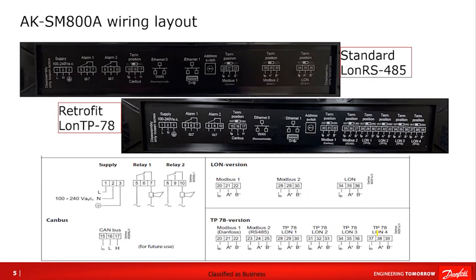On the back of the cover plates, you'll see a sticker that gives you a layout of the relays, the purpose of each, and numbering on the terminals — very helpful for someone working on the unit. On the right side, just as pictured previously, you'll see two Modbus plugs and then a third plug for Echelon communication. There is a terminal switch for termination above each of these plugs.